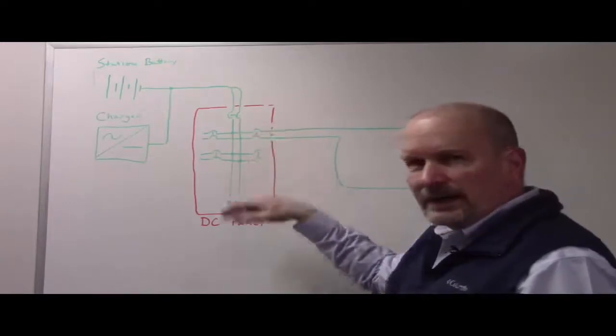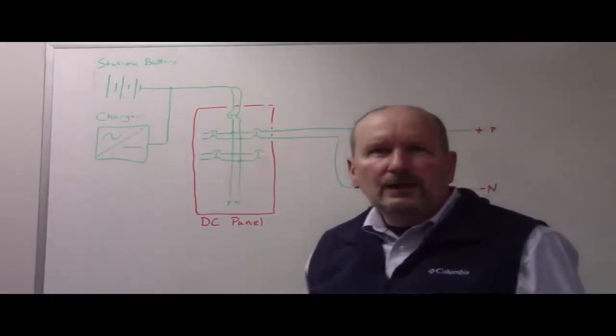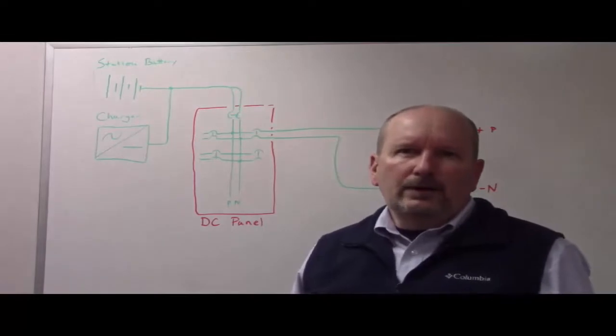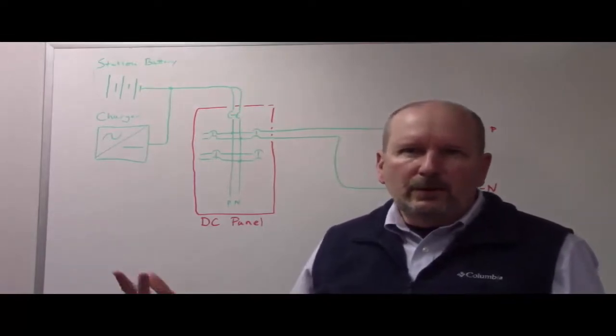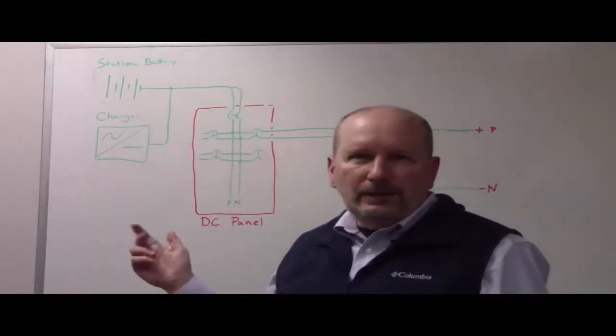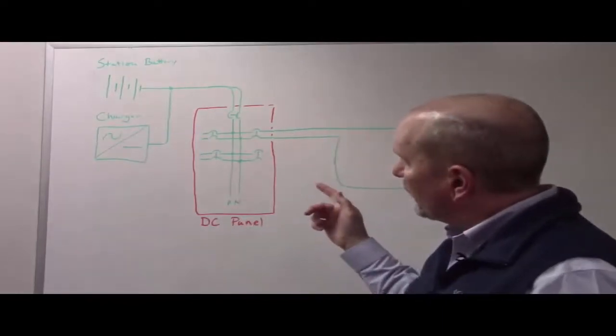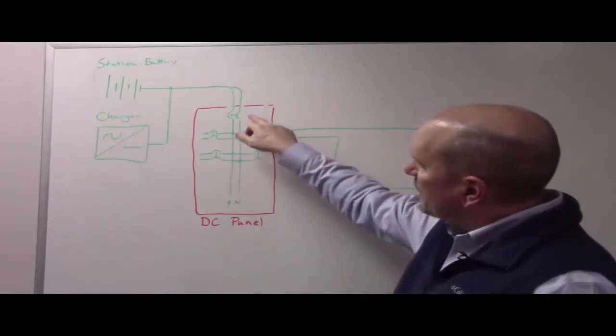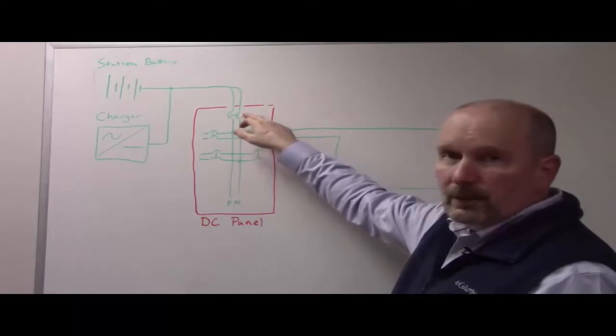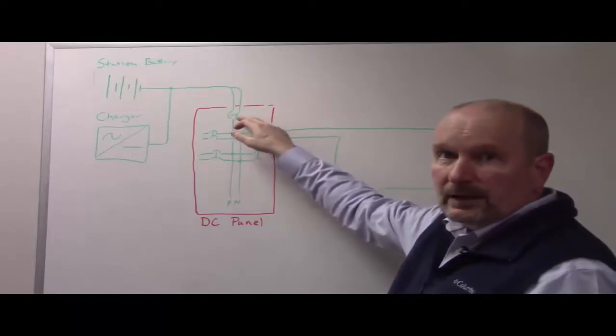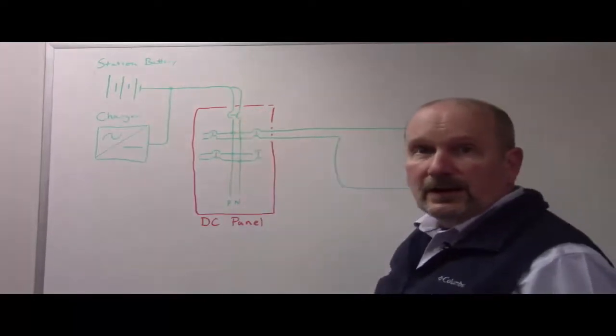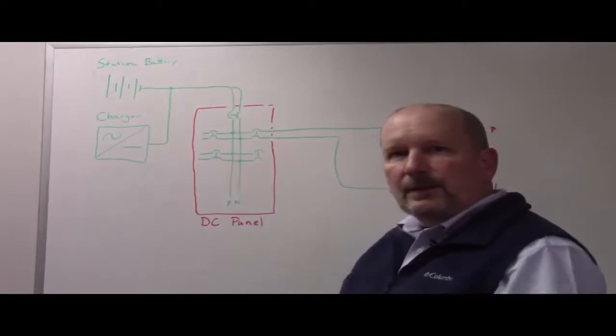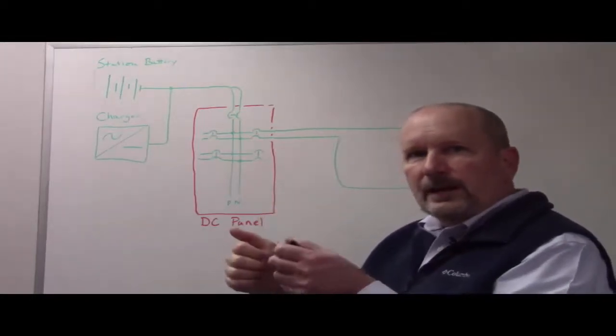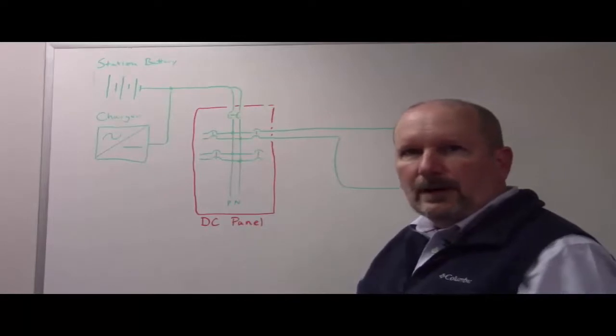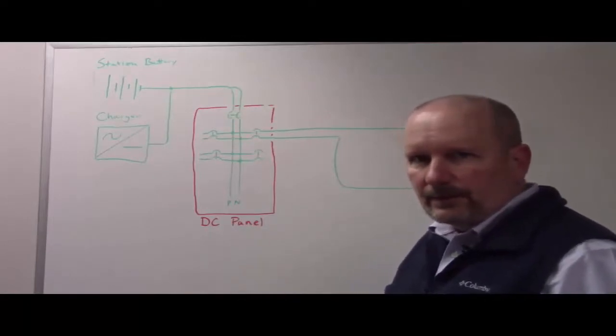This panel is actually similar to the one in your house. In fact, if you have a 120/240 system that's a 2-pole system, they'll look really similar to this. One difference is this symbology: basically it's a molded case circuit breaker, with a little line between the 2 poles indicating they're ganged together, meaning if one pole trips, it automatically trips the other pole, completely de-energizing the circuit.